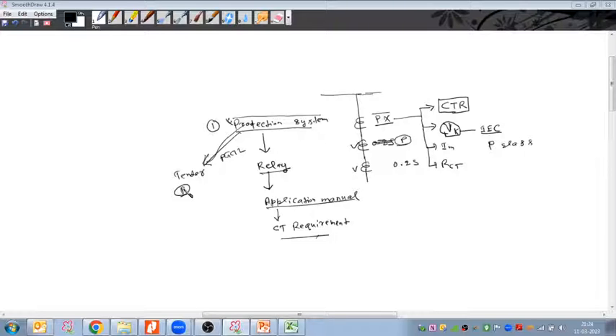Or if you are working for a particular utility, suppose you are not connecting your substation with the national grid. In India we have many states, and each state has its own utility. So you can refer to that particular state utility's protection philosophy, and based on that you can select the protection requirement, then the protection relay, then the application manual, and then the CT requirement. Ashwin, hope this helps you. Yes, we have to follow their protection philosophy, because ultimately you are going to connect with their system, so you can adopt that system's protection philosophy.